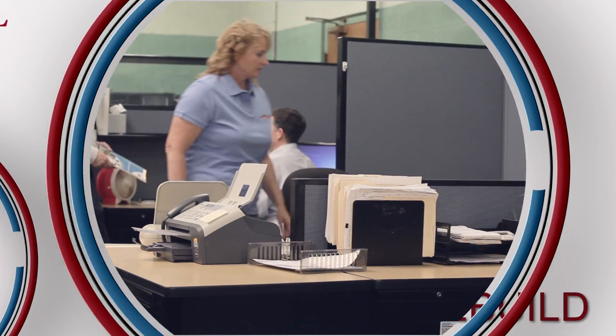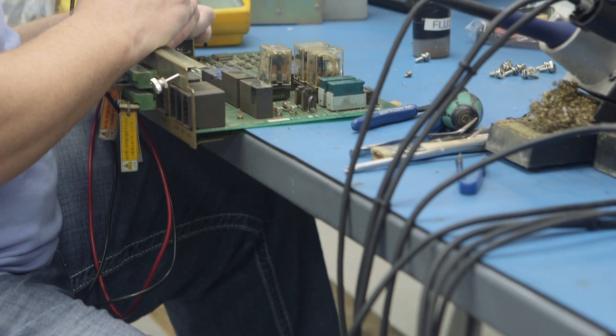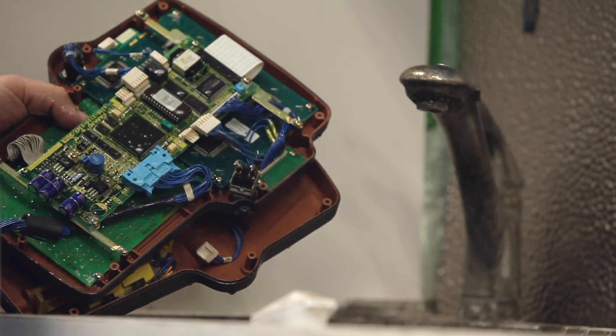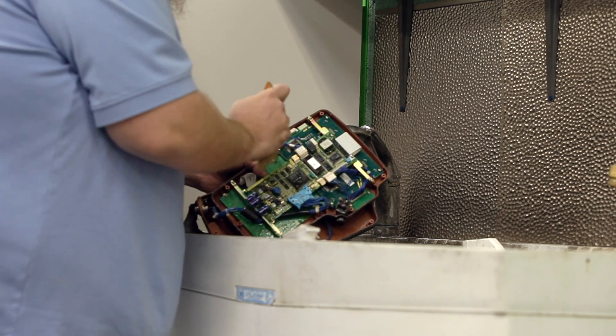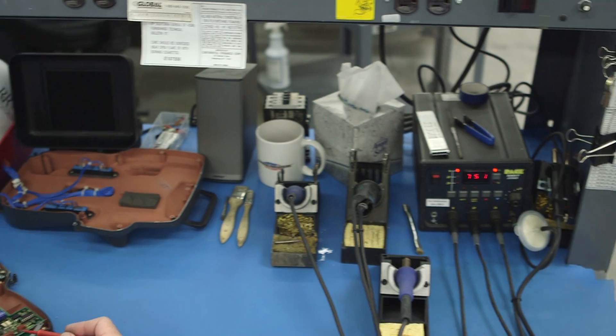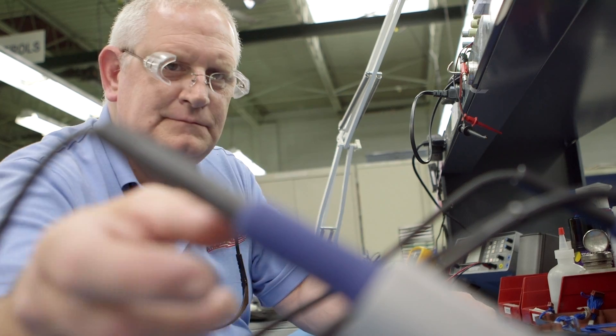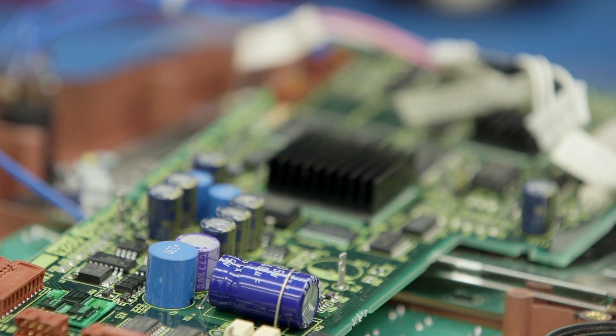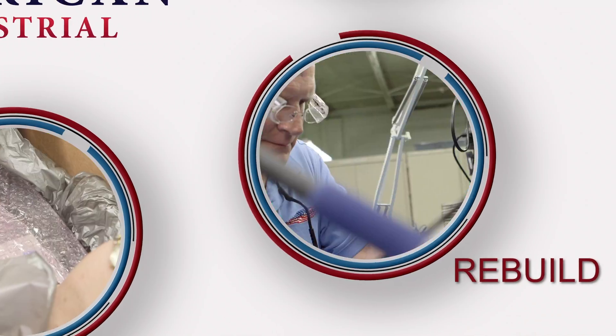When a repair authorization is received from your office, any special or non-stock parts are ordered, and one of our technicians continues service on your unit. Your unit is thoroughly cleaned to remove all contamination, both for cosmetic reasons and to eliminate the possibility of intermittent shorts or failures due to corrosion, metal filings, or other contaminants. All solder points are touched up and reinforced on edge connectors or other high-stress points, as well as any area suspected of cold solder joints. All aged, high-failure components — such as capacitors, relays, contacts, or others — are automatically replaced to prevent further premature failures.